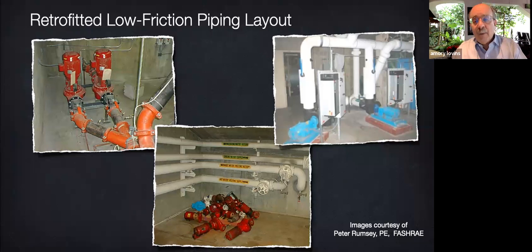Now, to help the pipe fitters understand how to minimize friction, he simply asked them to lay out the supply pipes as if they were drains, because in another part of their brain, they know that drain pipes, whose flow is driven only by gravity, not pumps, will clog if they're too small or if they have many elbows and joints, especially those right angle bends.